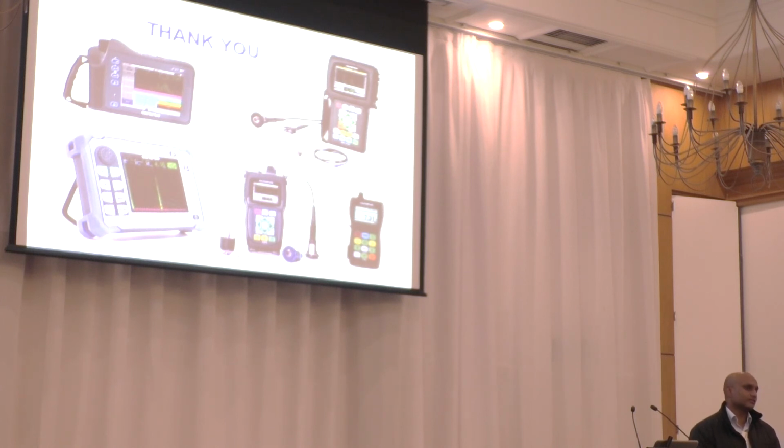In some of those difficult situations, what we can do is try different techniques or methods and then come up with something. Like I said, there's no one particular probe that can do it. Even with this coating software and a specialised probe, that's based on the properties of plastic or plasticky type coating. But when it comes to aluminium type coating, which is slightly different, I don't think the coating software will work. We'll probably have to work through the echo. But there'll be some testing that will need to be done.